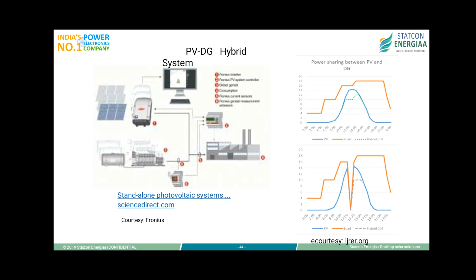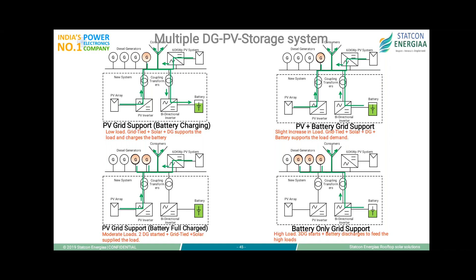This is a very typical scheme used with DG sets. There can be one or multiple DG sets. This is more of a mini grid, as seen in Africa and similar areas. It can be used where there are multiple DG sets along with optional grid supply, solar inverters, and storage. On the left top, you can see only one DG set working along with PV. Once the load rises, multiple generators are turned on one after the other. Storage is there to support the battery—when load is less, the battery charges, and when there's excess requirement, battery power is used.